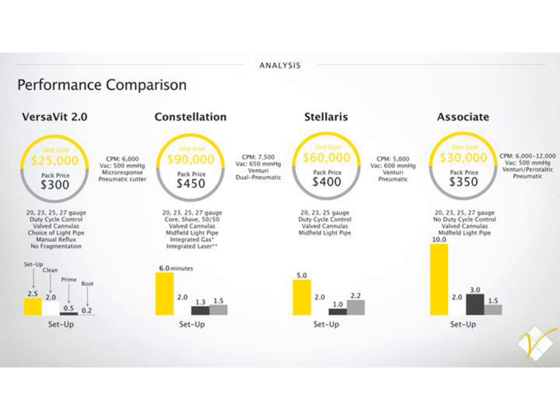The Associate certainly comes in at a very similar unit cost and similar pack price, but there may be some inefficiencies, particularly with the technical staff that you have and turnover and things such as that. When you look at the performance parameters such as cuts per minute, vacuum, the type of cutter that you're using, the size of the cutter, including the 20, 23, 25, and 27 gauge, you can see pretty much across the board all the machines have very similar parameters.